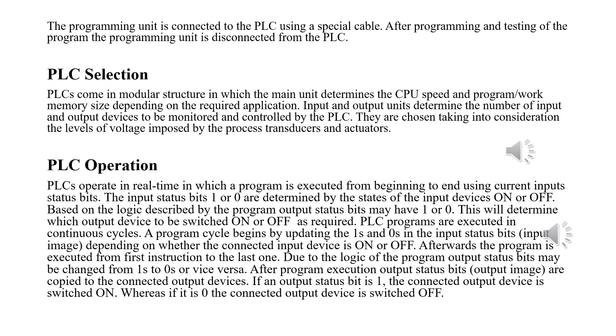During operation, the PLC executes programs in real time from beginning to end, depending on the current values stored in the input status bits. During program execution, the program may change the values of the output status bits to 1 or 0. The input status bits contain 1s or 0s depending on whether the connected input devices are on or off, and during program execution you write 1s or 0s to the output status bits depending on the required switching of the output device. We have an input image containing the input status bits and an output image containing the output status bits.